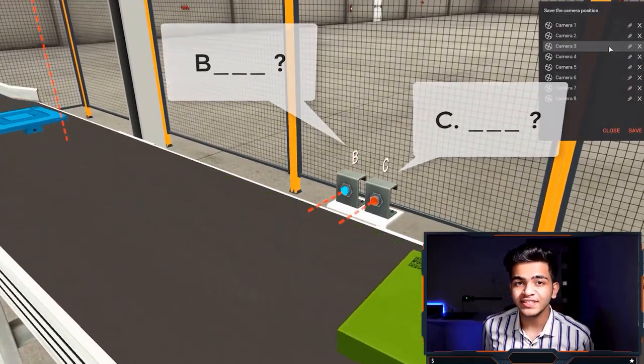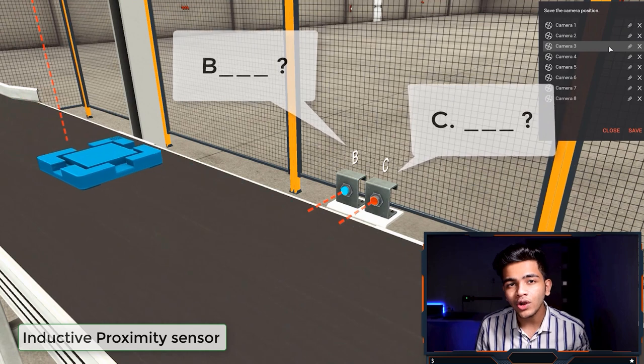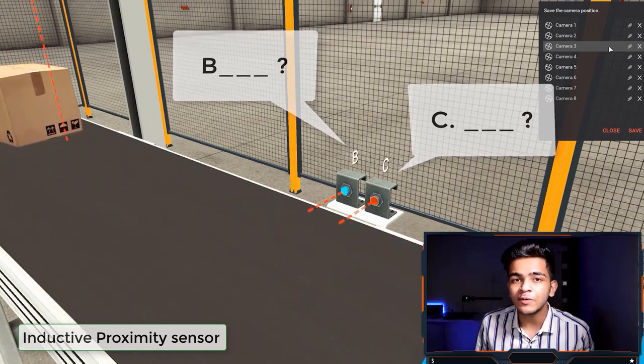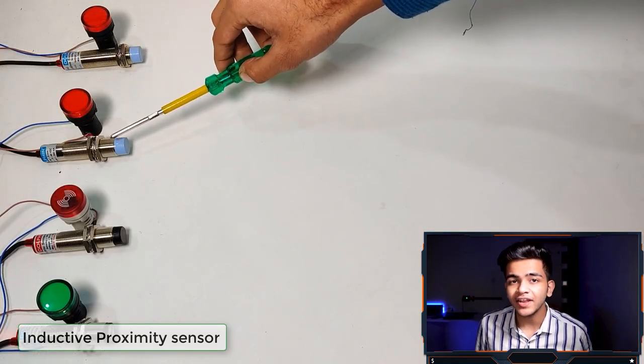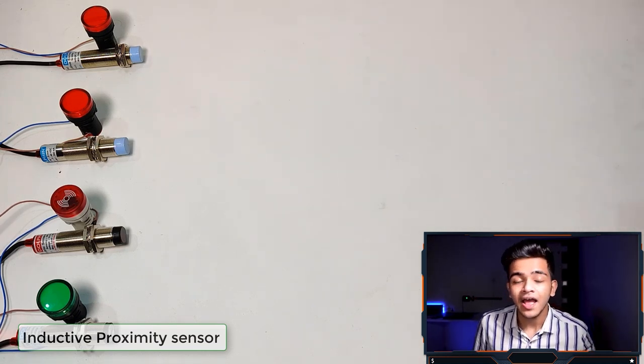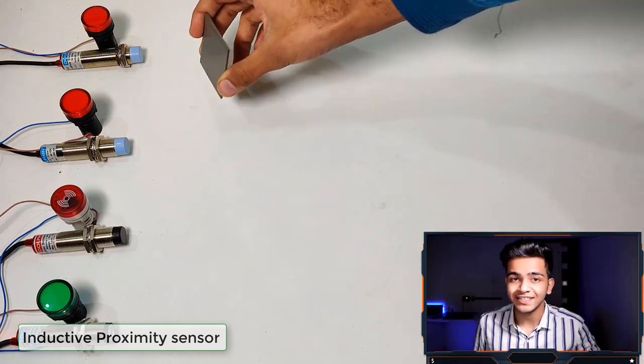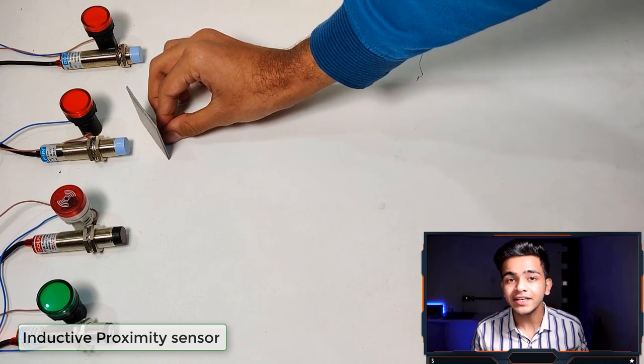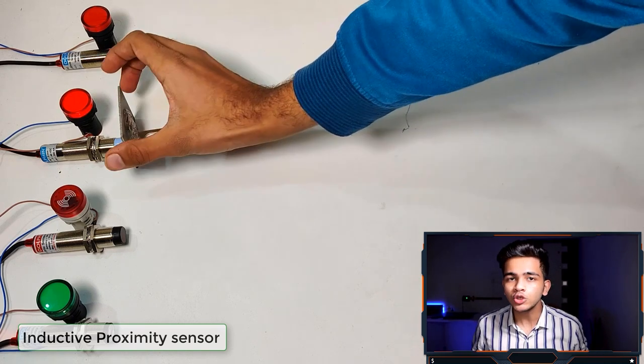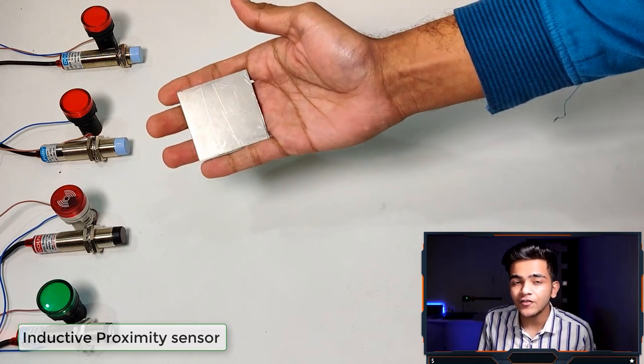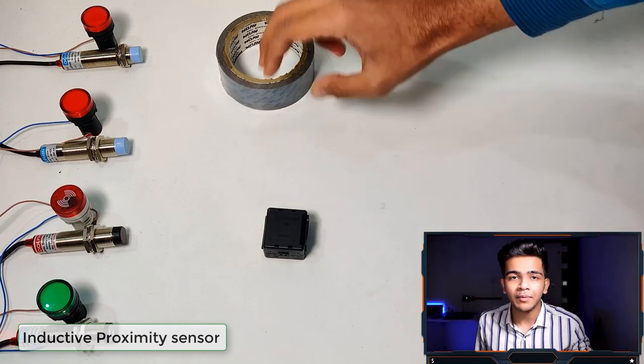The third sensor, Sensor C, is an inductive type proximity sensor. An inductive type proximity sensor will only detect metallic targets. The working principle is electromagnetic induction using the concept of eddy currents. When any metallic target comes within range of the sensor, it is detected. The sensing range increases with the diameter of the sensor — greater diameter means greater sensing range. Typically the sensing range of an inductive proximity sensor is about 2 mm to 15 mm, depending on the sensor's diameter.